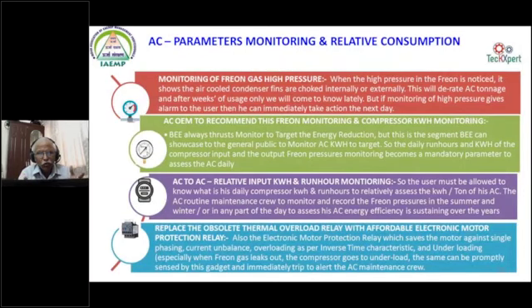A gauge can cost a few hundreds, but what it is monitoring is very critical to us. The suction and delivery pressure of the pump is very critical to us for energy conservation or for process optimization. Coming to the air conditioners, what monitoring and relative working can be done is, as I said, the freon high gas pressure means the condenser is getting choked, and this is the area where it can be monitored and prompt action can be taken.